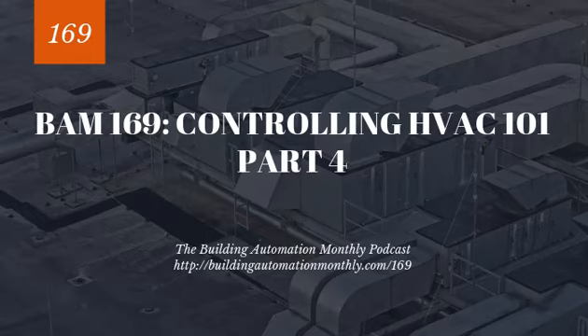But as a controls person, we are typically focused on one of two things, right? So we're either focused on simply enabling the boiler and maybe sending a 0 to 135 ohm resistance signal to the burner control to control our fire rate or temperature reset. So that's one way.